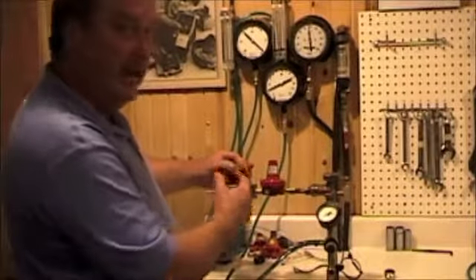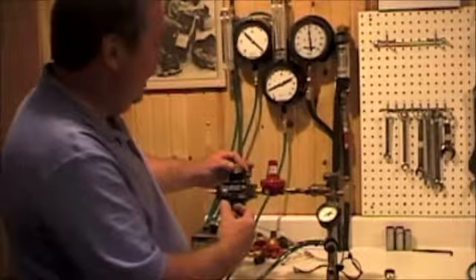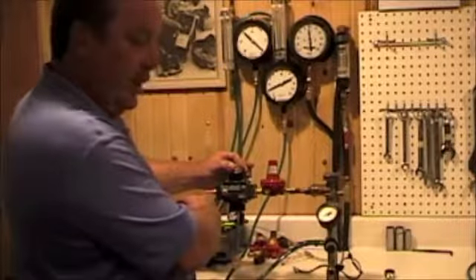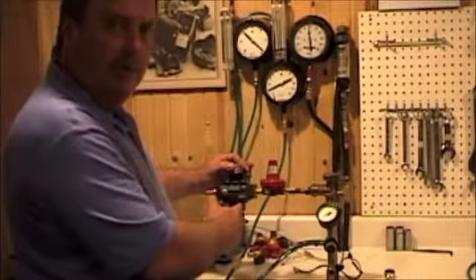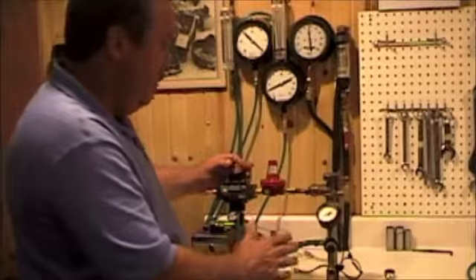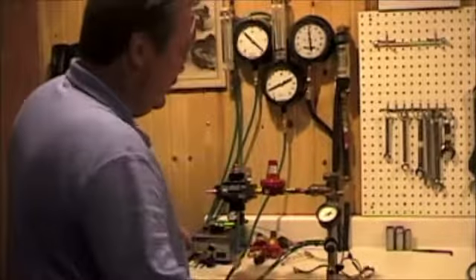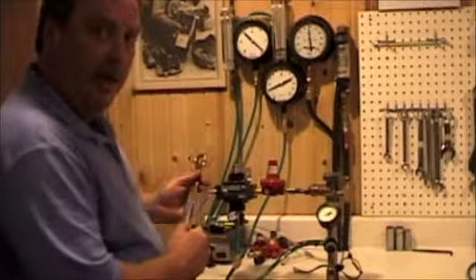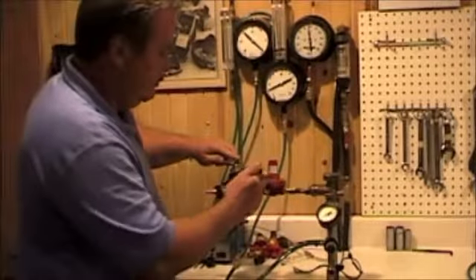Now I'm backing off on it, taking spring pressure off, and you can clearly hear the propane is starting to flow again. We're going to call that our start time, 5 pound start time. We're happy there. I think if I run this and tighten down the assembly, and that will be the end of adjusting start time.